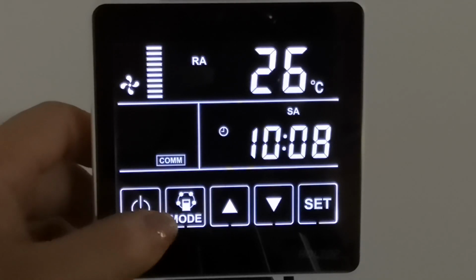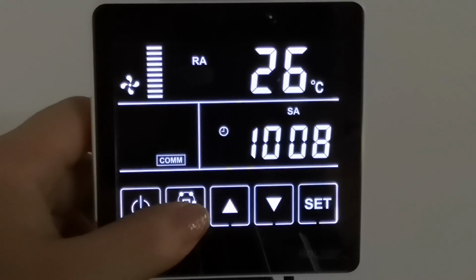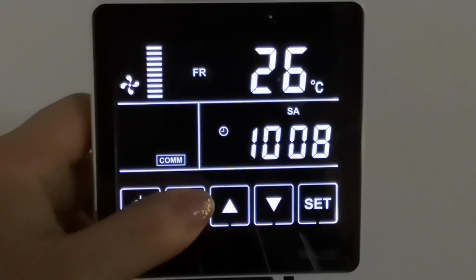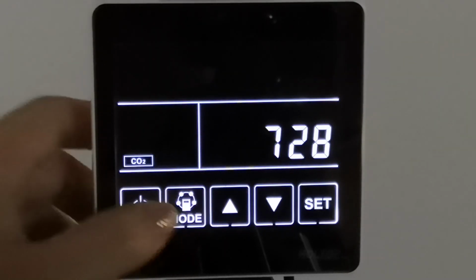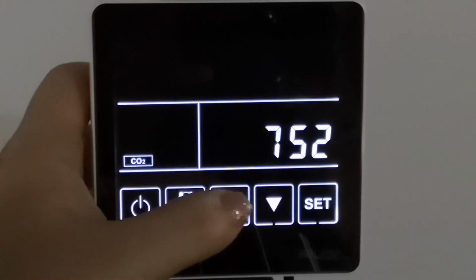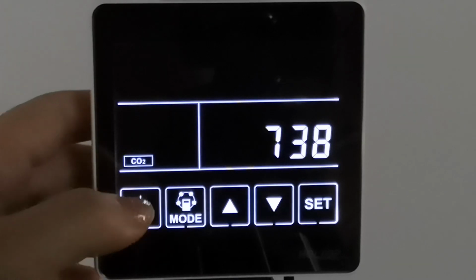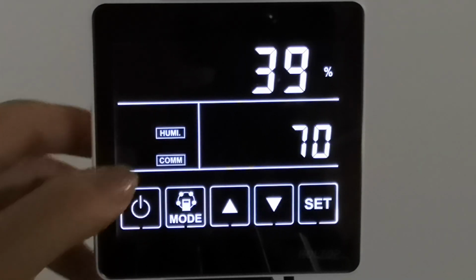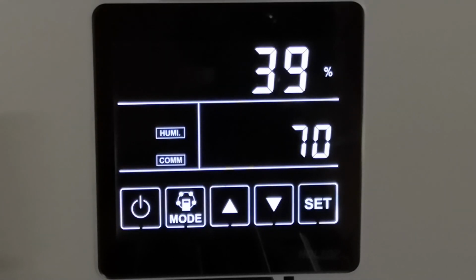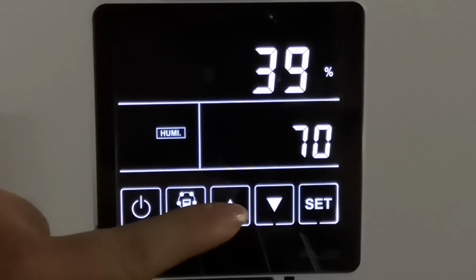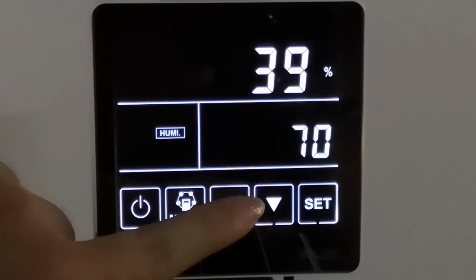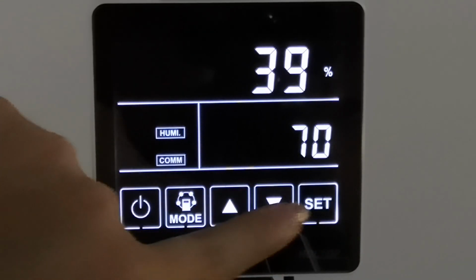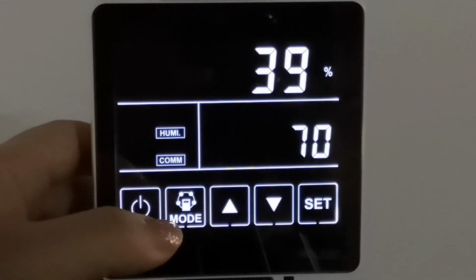The CO2 symbol appears on the panel if your ERV is connected to a CO2 sensor. The ERV runs at high speed when the CO2 concentration is higher than the setting value for more than 5 seconds. The humidity symbol appears when the temperature and humidity sensor is connected to your ERV, and your ERV will run at high speed automatically when humidity is higher than the setting value for more than 5 seconds. When you are setting the humidity, you can adjust the target humidity by pressing the up and down buttons. The setting range is from 50% to 100%. The default value is 70%.